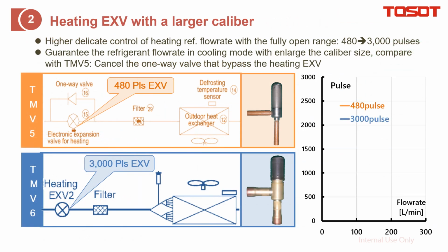Bigger size for the heating EXV. First of all, this heating EXV locates at the outdoor unit for the heating metering. Specifically, it locates at the outlet of the outdoor heat exchanger. And also you can find that for our last generation, here is the EXV. It just bypass with a check valve. Do you know why we need to set a check valve here to bypass this EXV for our last generation?